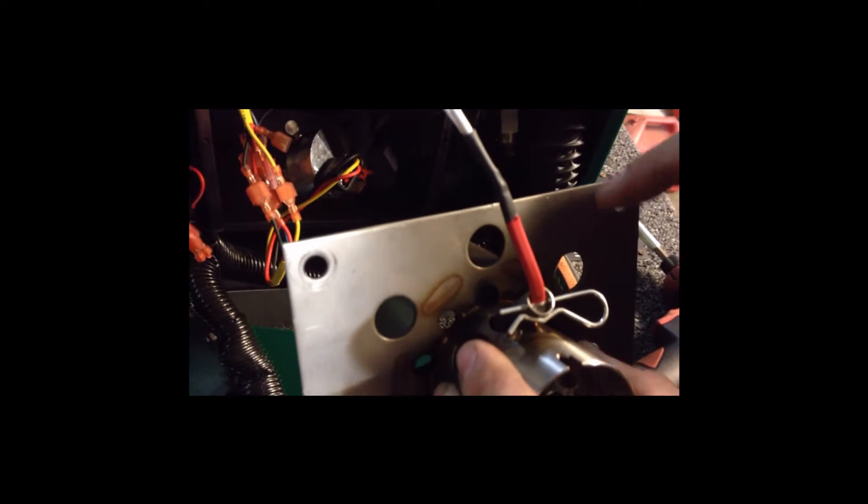Now that you have that burn tube out of there, you can clean the inside of your water jacket. Get in there with some steel wool or some Scotch-Brite, and just kind of break up the crust that's built up. Vacuum it out, clean it out. Then you can go back over to your burn tube and replace the igniter before reinstalling the burn tube.